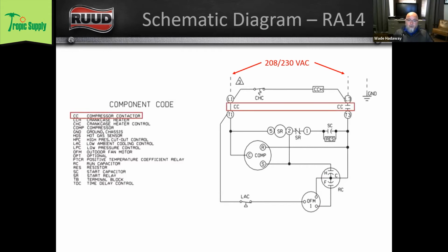You can see it's showing us our contactor. I can determine from looking at this drawing that the contactor that we have is a single pole. It's a double pole, sorry, single throw double pole contactor. We've got an open set of contacts between L3 and T3, and then we've got a brass bar between L1 and T1. We've got our line voltage coming in, and everything on the back side of the contactor, from the contactor to the loads, is called the load voltage. We've got line voltage coming in, we've got load voltage coming out.